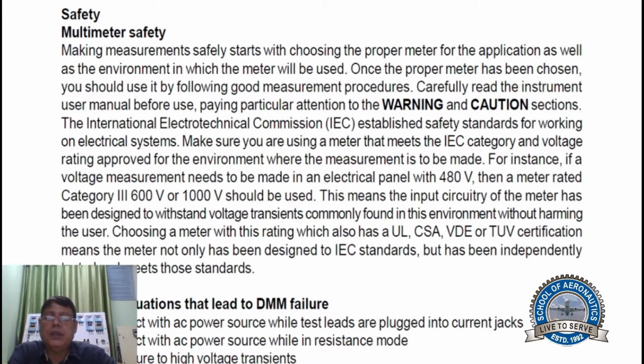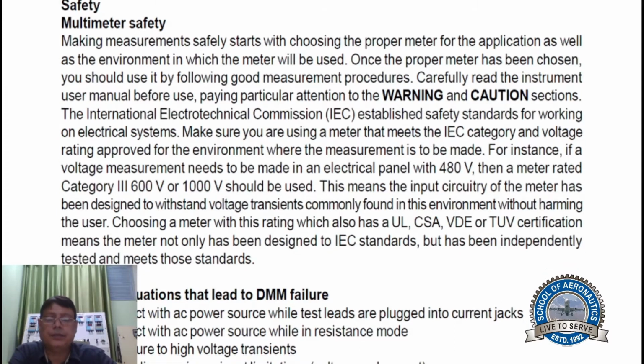Choosing a meter with this rating, which also has a UL, CSA, VDE or TUV certification, means the meter not only has been designed to IEC standards but has been independently tested and meets those standards.